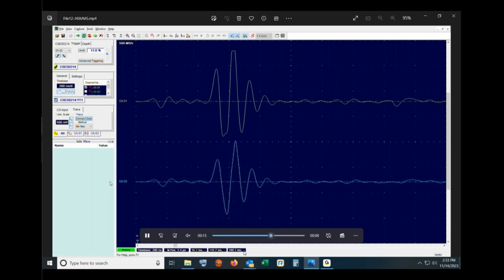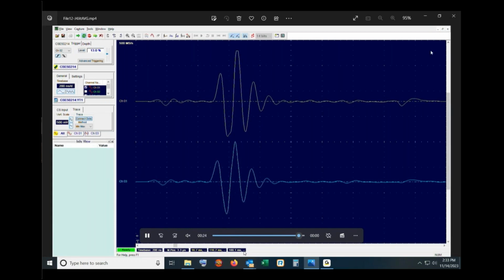The downside is I can't move as fast because I'm not just taking one waveform per position, let's say. I have to take 400. That sort of illustrates a general principle that the longer I measure, the better measurement I get. This sort of translates into, the higher sampling speed you want, the less maximum resolution is available typically.